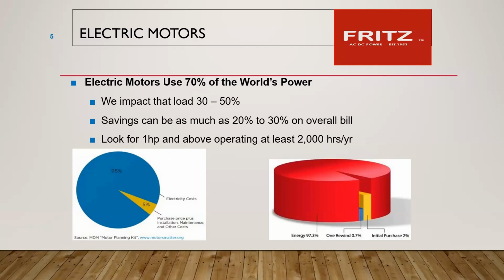I had a question from P here. I have a 5 horsepower table saw, and he has single phase power in his workshop. Will an inverter make that work? Yes, definitely it will. If you're not going to be using the table saw very heavily, you could get by with a static converter, but a variable frequency drive will give you full torque and power for that, and make the motor run more efficiently and operate and last longer.